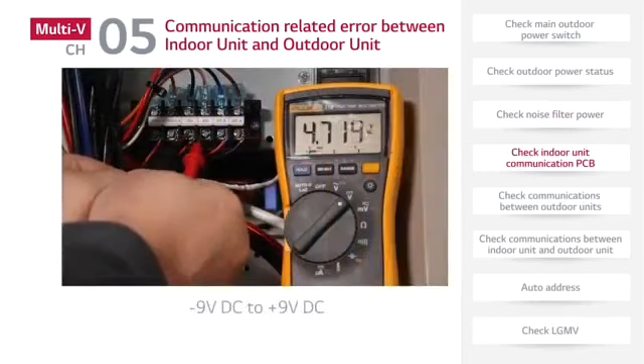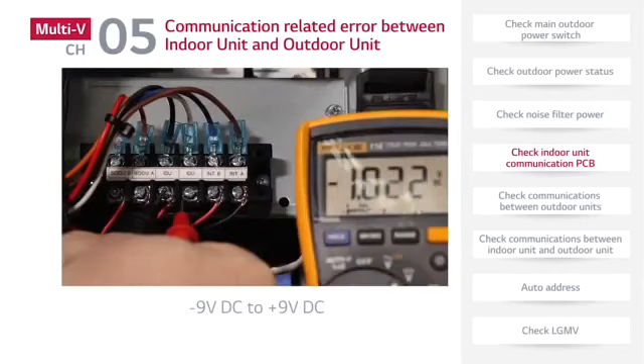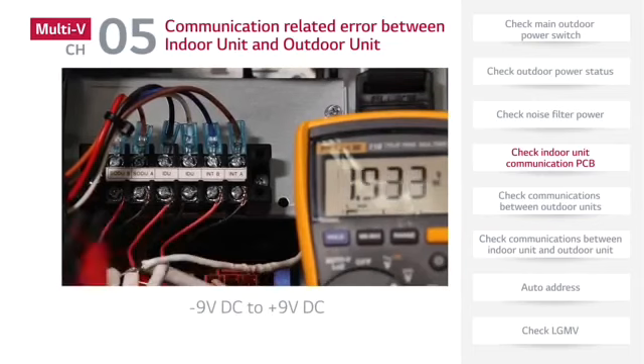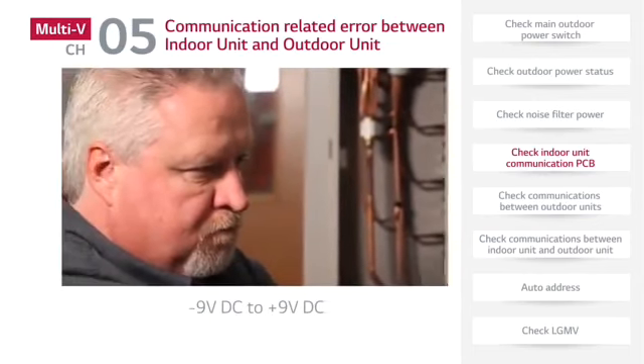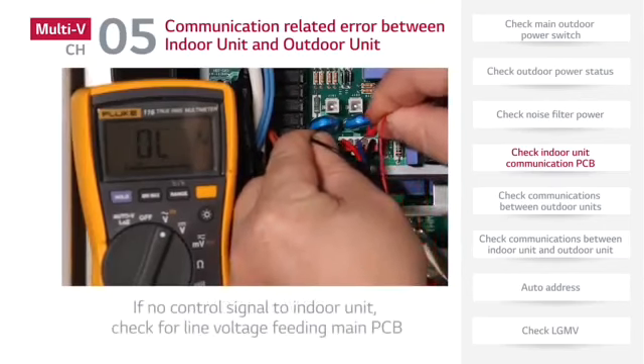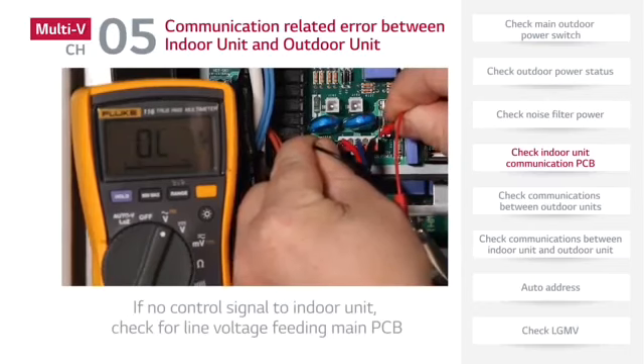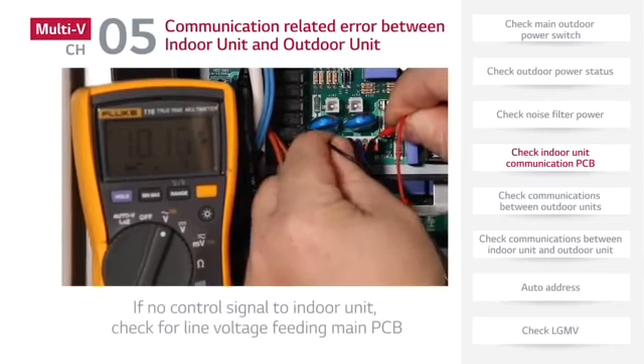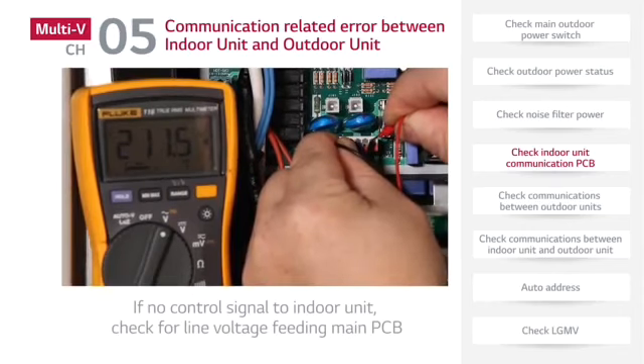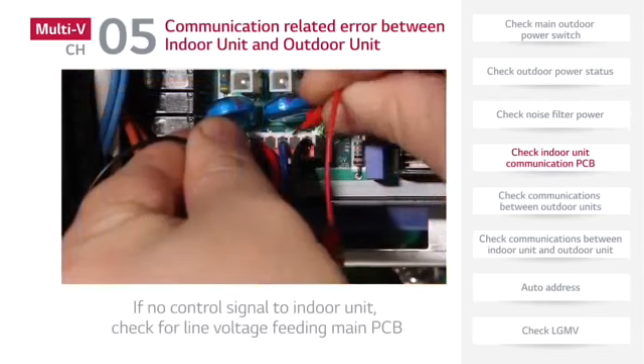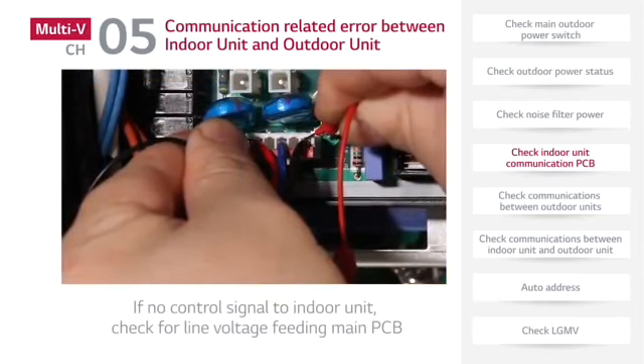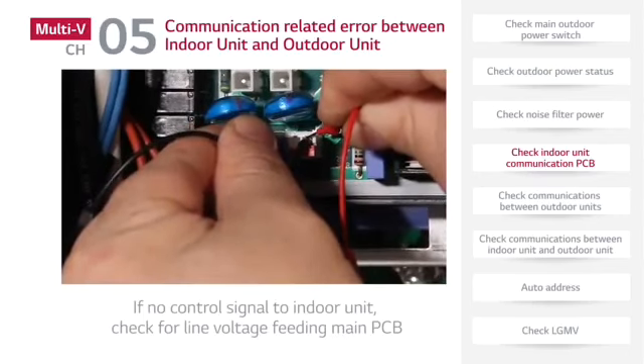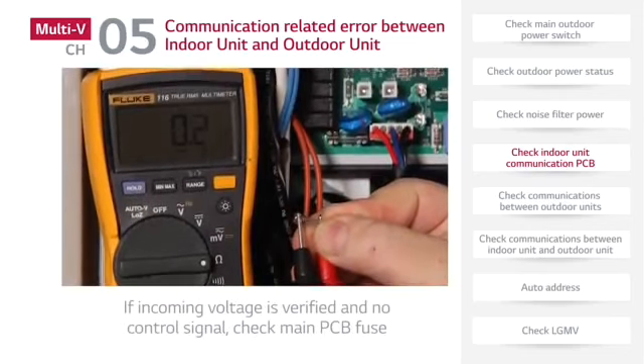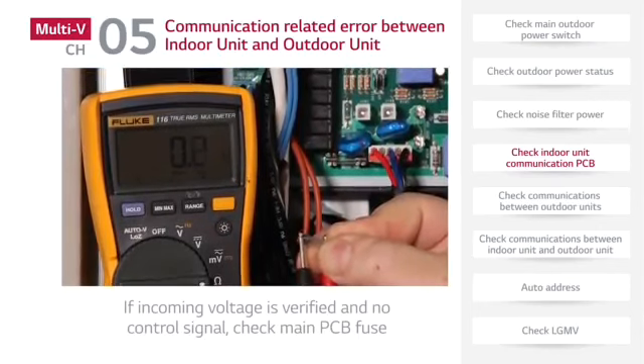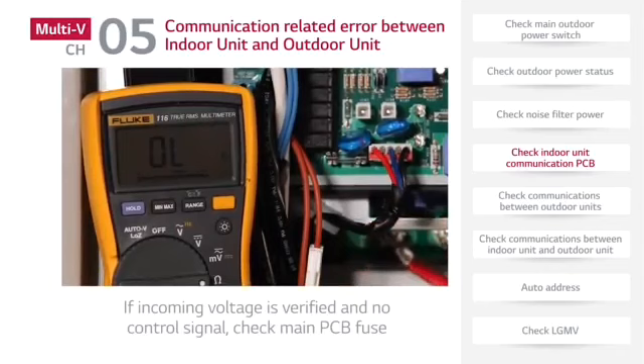If the output voltage of the noise filter is normal, the next step is to check the main PCB communication signal. The normal voltage value for the communication signal should vary from minus 9 volts DC to plus 9 volts DC. If there is no control signal to the indoor units, check for line power feeding the main PCB. If there is no power feeding the main PCB, inspect the filter PCB. If the incoming voltage is verified and there is no control signal, check the main PCB fuse. If the fuse tests good, replace the main PCB.